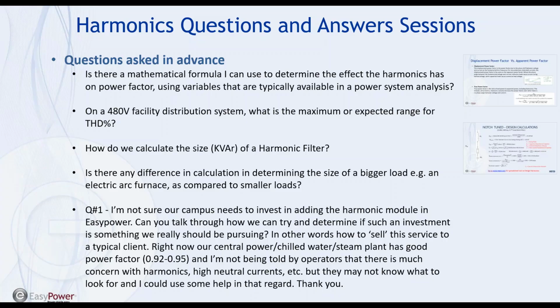And it's very typical that, from my view, I always ask for the very large VFD drives. Tell me what the large harmonic producing devices are, and those get modeled and I concern myself less with the smaller loads, computer loads, incandescent lighting, things like that. I'm typically not as concerned with those, especially at the medium voltage level. So I think I answered that question.